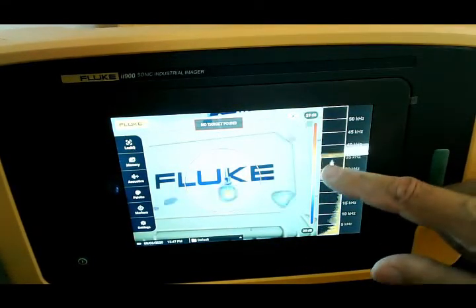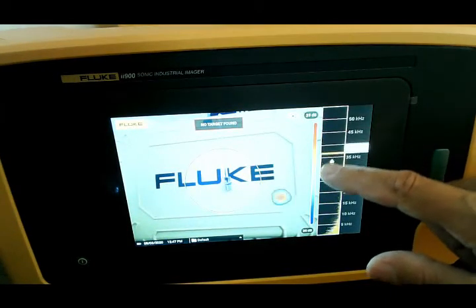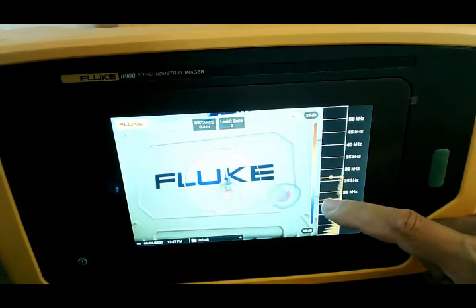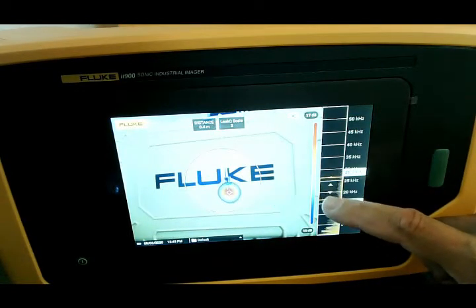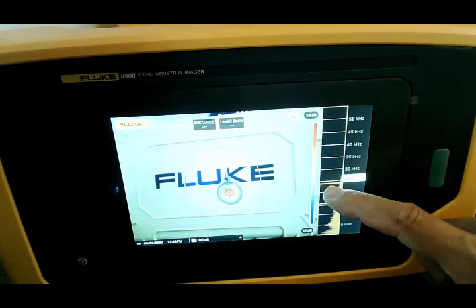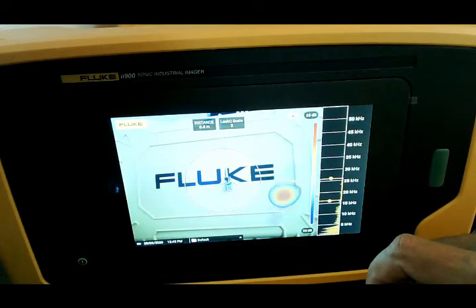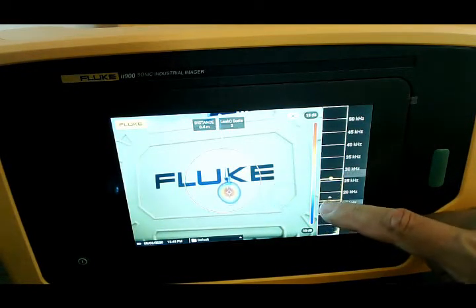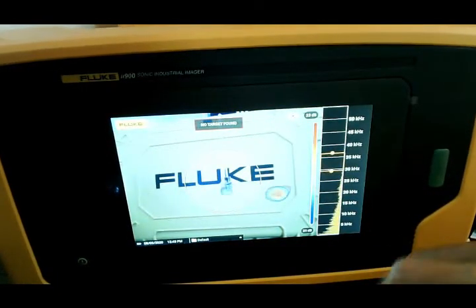On the right hand side here is our slider. This is going to allow us to pinpoint a potential leak. As I slide this up and down, we notice the true leak right there, and then the reflection keeps popping up — that is the echo of my voice as I speak. So I can actually filter myself out and focus on just the leak.